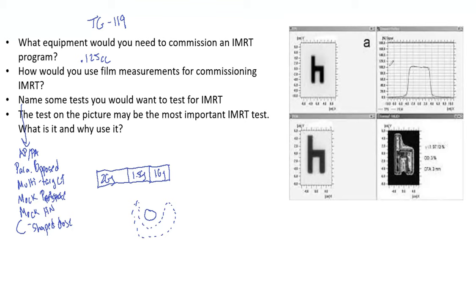Now, the picture to the right — I think the most important test — is called the Van Esch test, and a lot of people know it as the chair pattern or chair test. This tests the sliding window and the inverse planning system. It shows the quality control for inverse planning, the leaf motion calculator, and the dynamic MLCs and their performance. You plan, calculate, and measure this chair pattern.